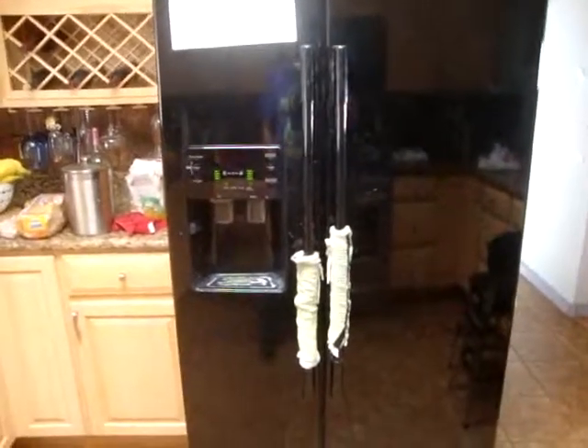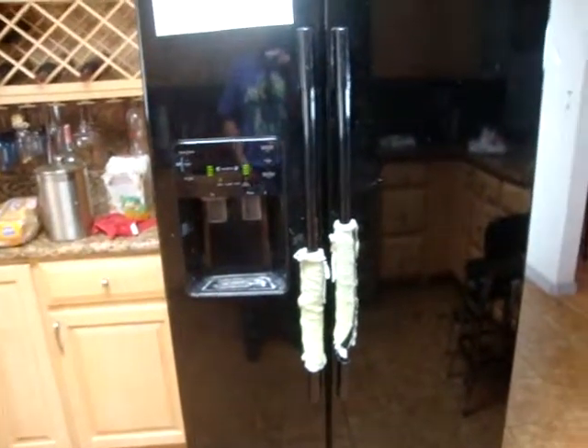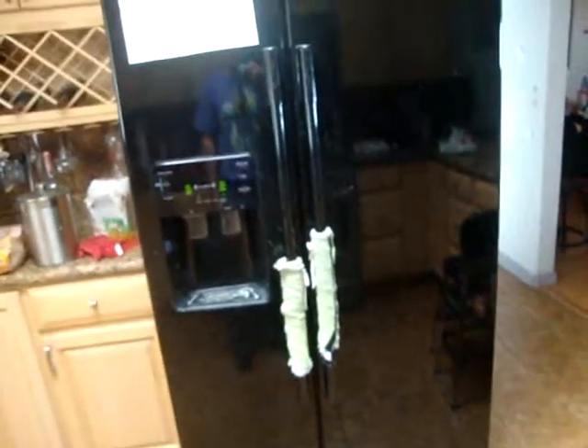You can see the refrigerator is cooling down like it should, and I'm hoping it will. It seems like I'm successful — the temperature is at 40 degrees Fahrenheit, which is good. I put some stuff in already — a cup of water — it's frozen solid! That's what I'm talking about. So I fixed it. I still have a little R134A left — I think I'll use it in my van. I can return the bottle for a $10 rebate. It looks like we're back in business. One little fan that died earlier and just charged the system — the fridge is back in operation.